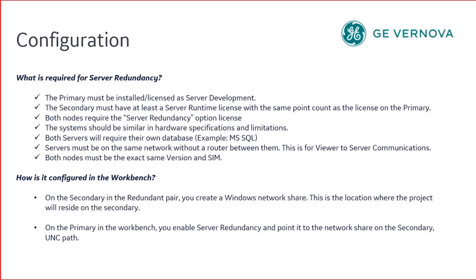What is required for server redundancy? The primary must be installed and licensed as server development. The secondary must have at least a server runtime license with the same point count as the license on the primary. Both nodes require the server redundancy option license. The systems should be similar in hardware specifications and limitations. Both servers will require their own database — for example, a SQL database. Servers must be on the same network without a router between them for viewer-to-server communications, and both nodes must be the exact same version.